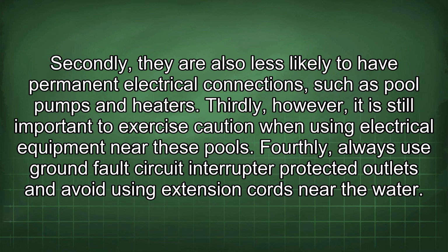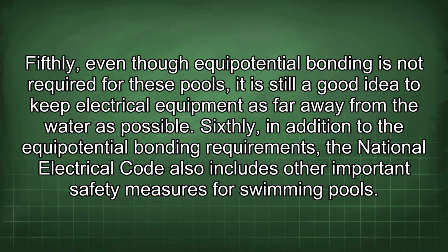Fourthly, always use ground fault circuit interrupter protected outlets and avoid using extension cords near the water. Fifthly, even though equipotential bonding is not required for these pools, it is still a good idea to keep electrical equipment as far away from the water as possible.